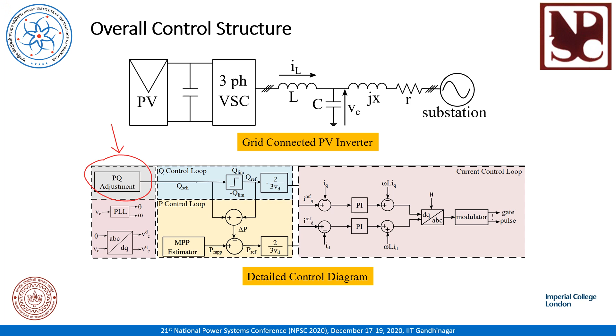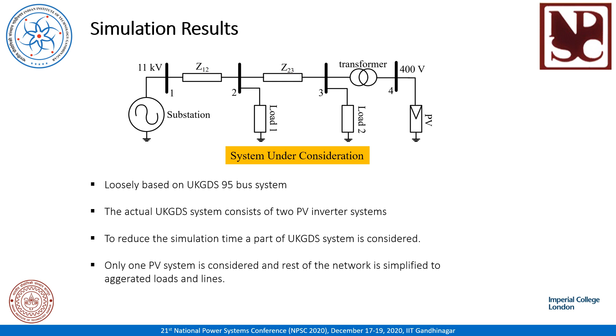To validate the proposed technique, the system under consideration is shown here. The system is loosely based on the UKGDS, or UK Grid 95 bus system. The actual UKGDS system consists of two PV inverters. However, to reduce the simulation time, a part of the UKGDS system is considered for the simulation. In this system, as you can see, only one PV system is considered and the rest of the network is simplified to the aggregated load and the lines.